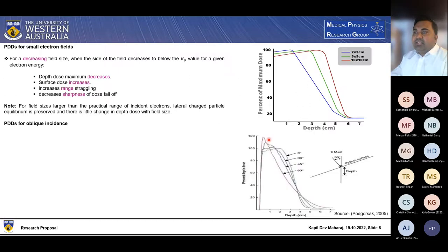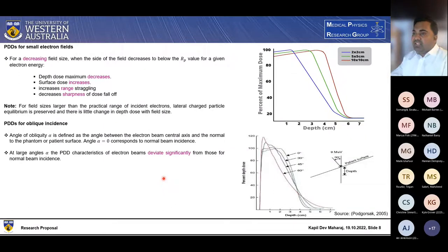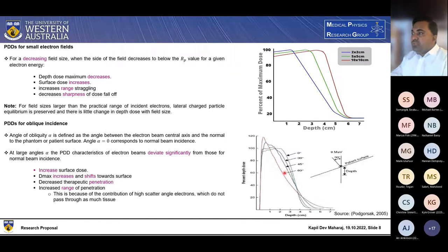Percentage depth dose for oblique incidence. So in terms of the oblique or gantry angle, angle of oblique alpha is defined as the angle between the electron beam central axis and the normal of the phantom or patient surface. So as you can see, this angle is known as alpha and when alpha is equal to zero, which corresponds to the normal beam incidence. At large angles alpha, the percentage depth dose characteristics of electron beam deviate significantly from those from the normal beam incidence, such as increase the surface dose. As you can see from this figure, D max increases and shifts toward the surface, decreased therapeutic penetration, increased range of penetration. This is because of the contribution of high scattered angle electrons, which do not pass through as much tissue. So oblique effect becomes significant for angle of incidence alpha exceeding 45 degrees as we can see from this figure.